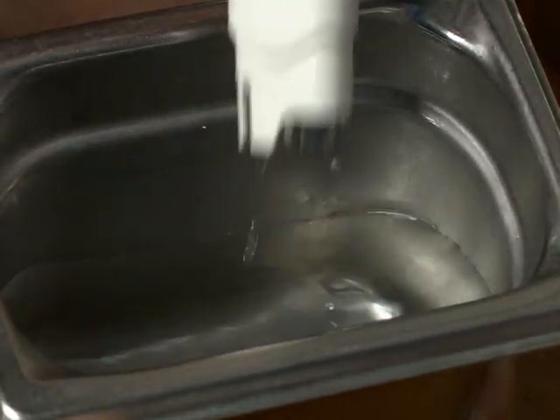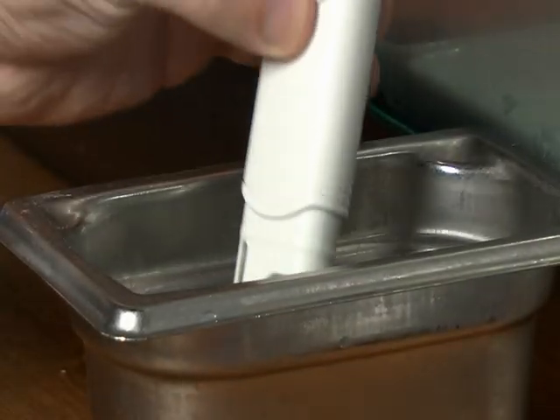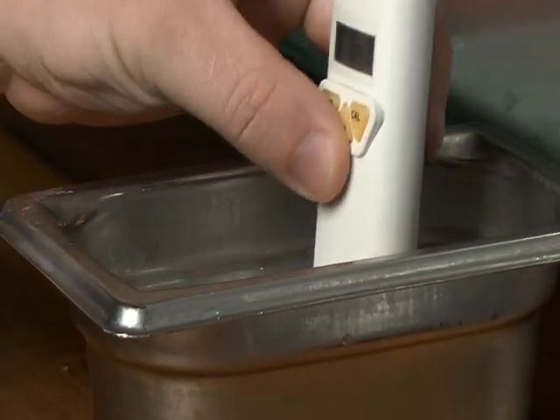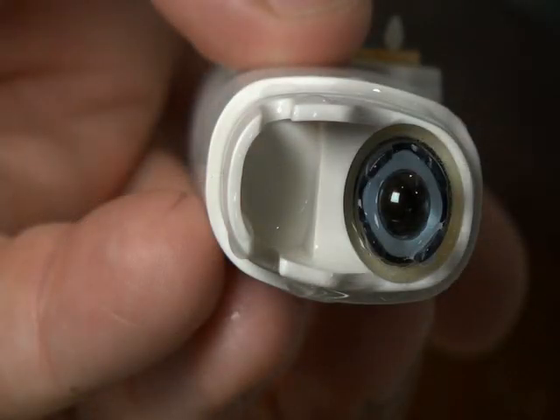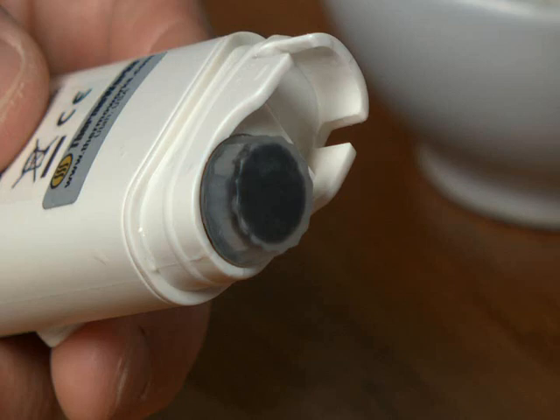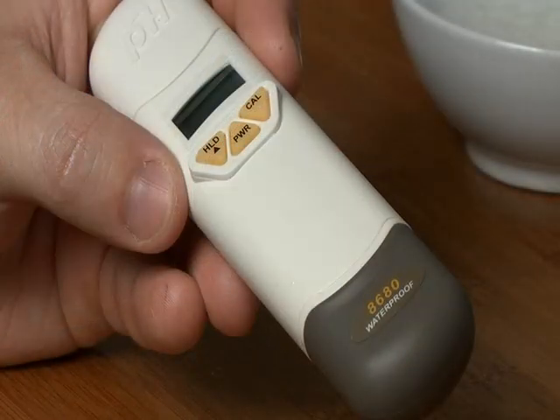Clean the pH electrode by vigorously swishing it in distilled water or under running water, or as recommended by the manufacturer. It is essential that the pH meter be impeccably clean after each use to prolong electrode life and obtain accurate results. Do not use harsh chemicals or any chemical not recommended by the manufacturer to clean electrodes, as this can ruin them.